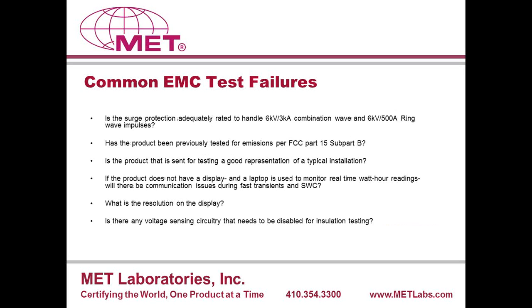So continuing with the ANSI test failures, what are some of the things that you should consider before sending a product down for testing? So starting with the surge test. As I mentioned previously, the surge test is performed at a very high amplitude of 6 kilovolts. And not only is it a combination wave surge test, but there is also a ring wave surge test. So there are two components to that surge test. The other thing to consider is that the combination wave surge test is performed at 6 kilovolts and 3 kiloamps.